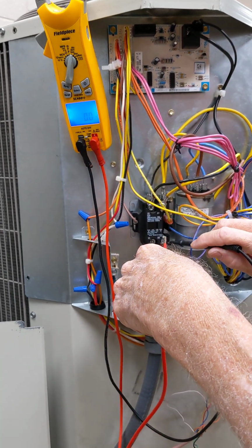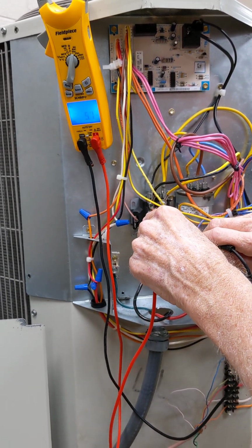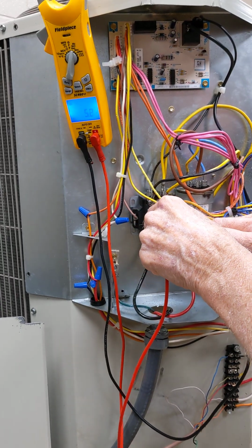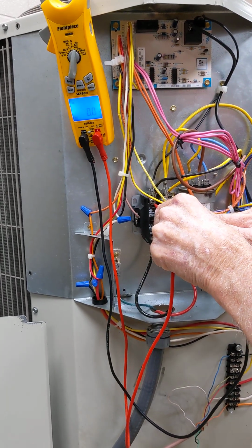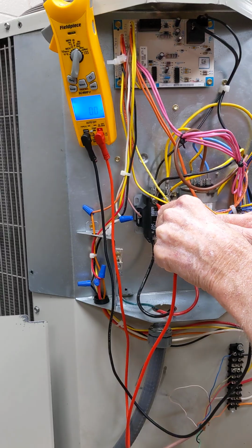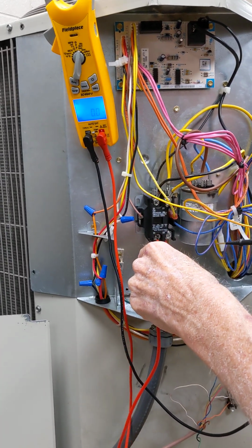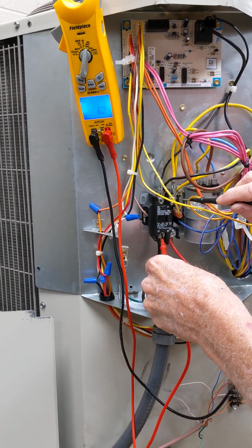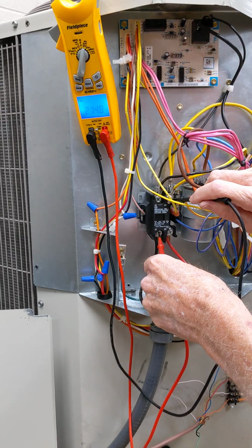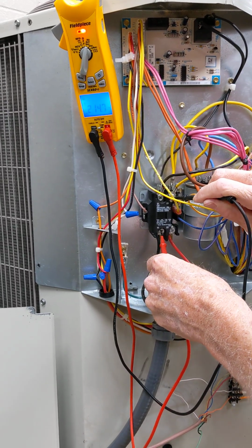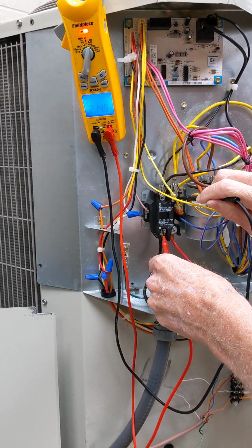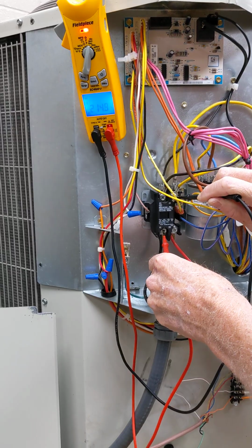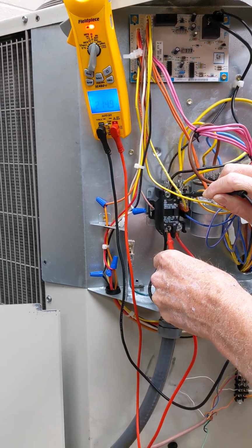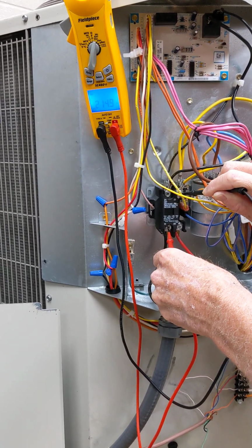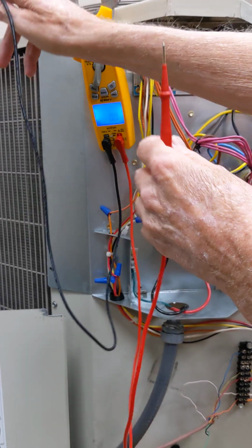So if I do crisscross applesauce and I go from the bottom of one side to the top of the opposite side, in this case I got a 0. And if I go from the bottom of the opposite leg to the top of the opposite leg, you got 215 volts. Okay, so it's a safety check. Crisscross applesauce is a safety check. And you can do it, this one doesn't have it.